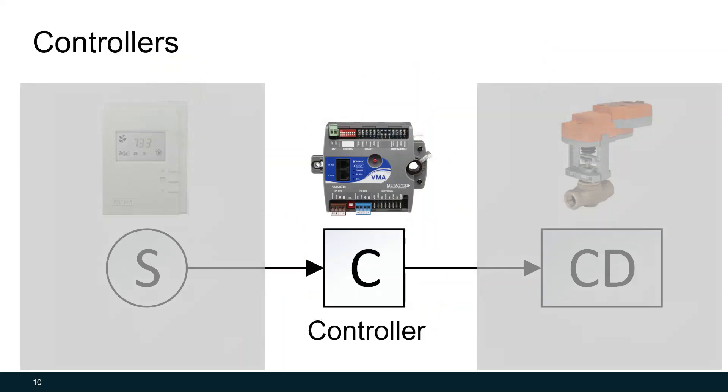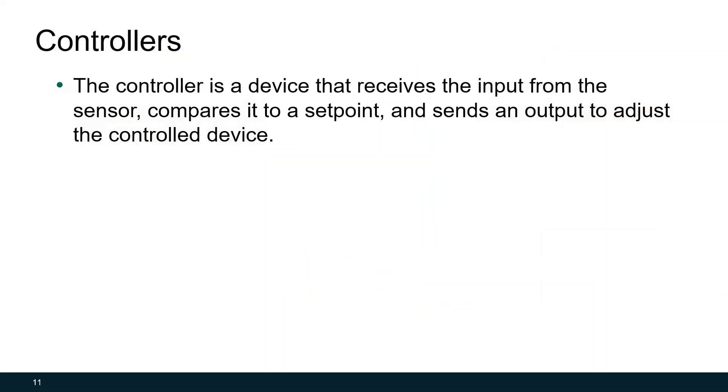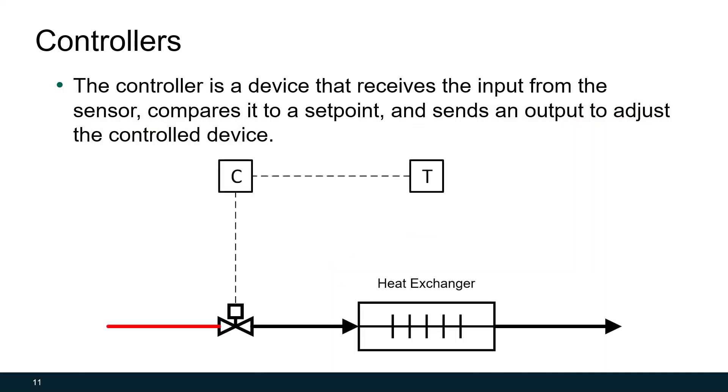So those input signals from the sensor are sent to the controller. What is a controller? The controller is just a device that receives the input from the sensor, compares it to a set point, and sends an output to adjust the control device. Let's go through an example to see how this works. Here we have a room that's being heated by a hot water heat exchanger. The temperature sensor, the input device, detects the space is at 68 degrees and sends that signal to the controller. The controller then compares it to its set point. Its current set point is 70 degrees. We're trying to maintain the space at 70 degrees. The controller detects that there's a difference between the input signal and the set point. And because it detects a difference, it sends an output signal to the hot water valve, the control device, to open. The control device will then open and then we can start heating the space.